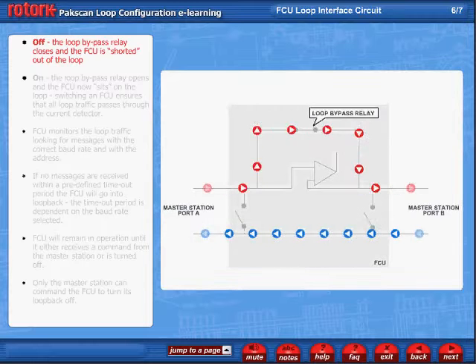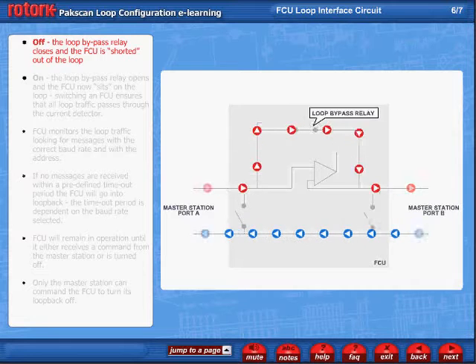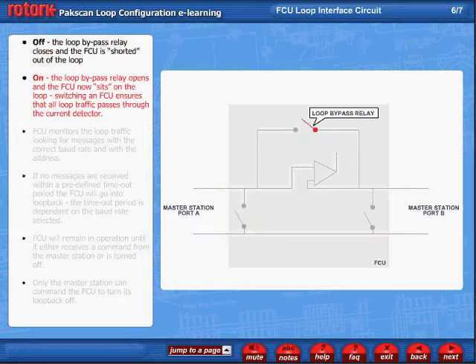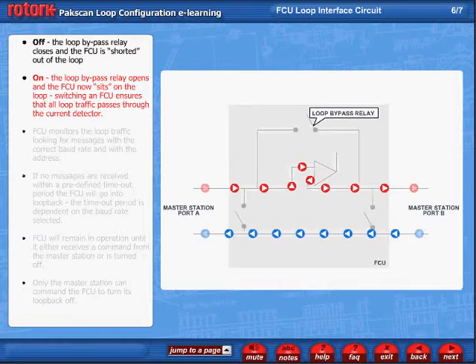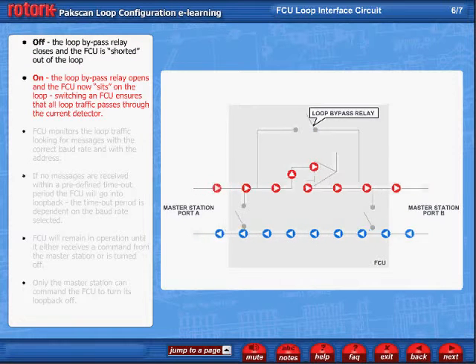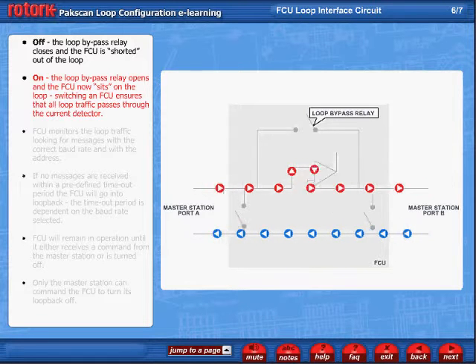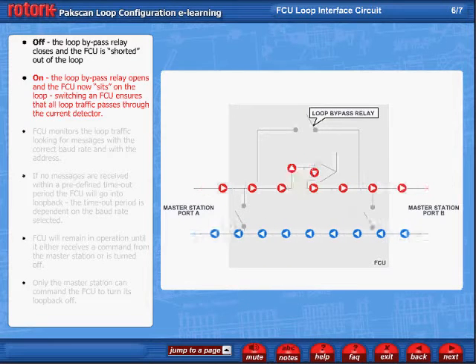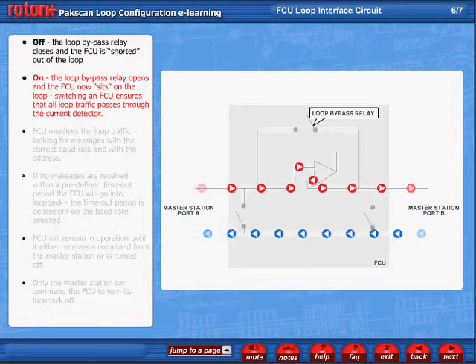When the FCU is turned off, the loop bypass relay closes and the FCU is shorted out of the loop. In contrast, when the FCU is turned on, the loop bypass relay opens and the FCU now sits on the loop. Switching an FCU ensures that all loop traffic passes through the current detector.